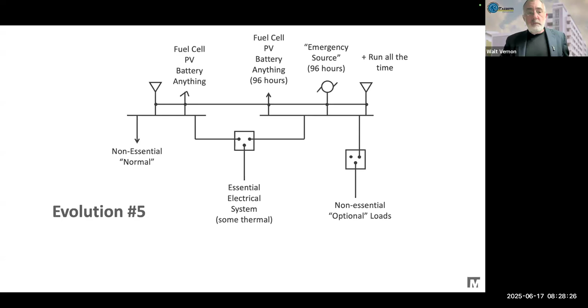The other thing that's happened, and I think this is highly significant, is that there's been a lot of work in the National Electrical Code around demand factors and the ways we size our systems. This is increasingly important because as we move to all-electric buildings, the rules around how we size our systems—both the buses and the on-site generation systems—are changing. For a long time, the codes have permitted emergency sources to be sized based on prudent demand factors and historic data.